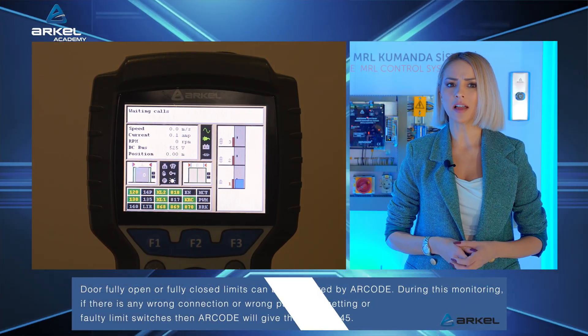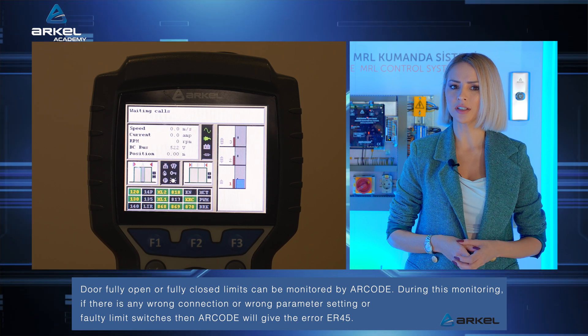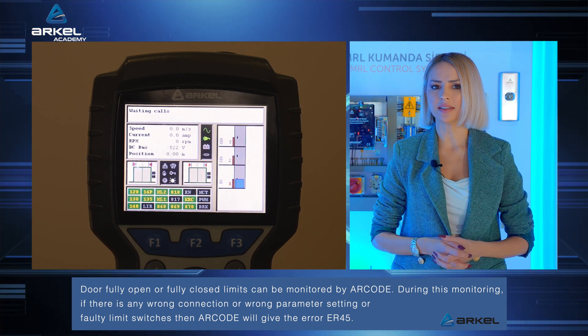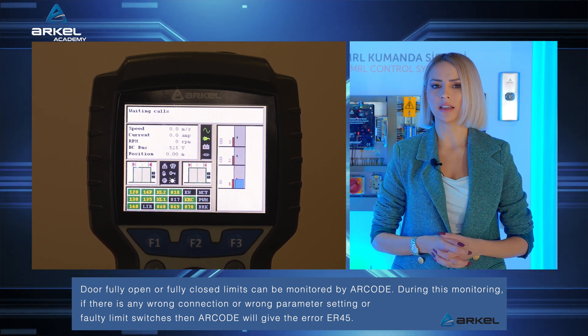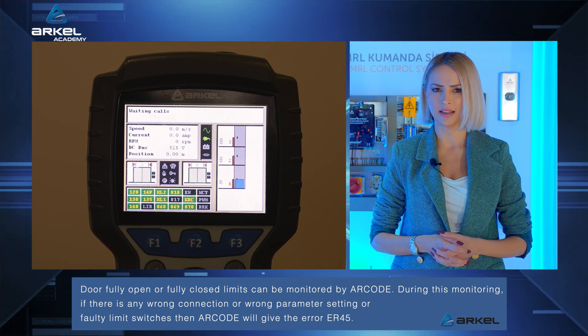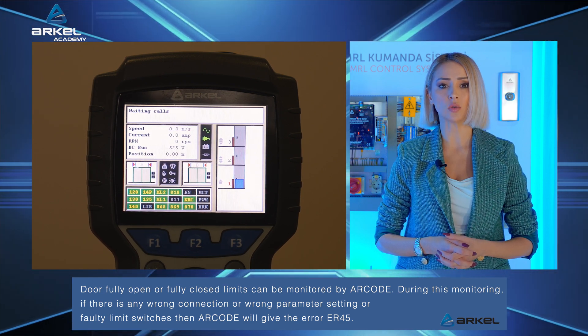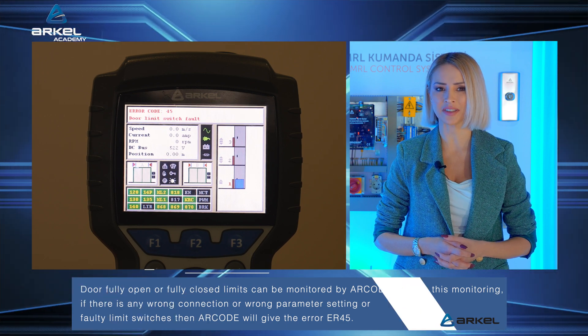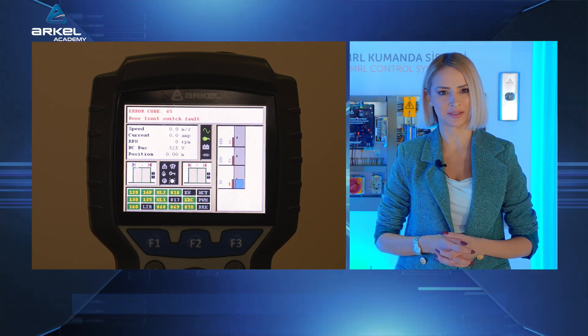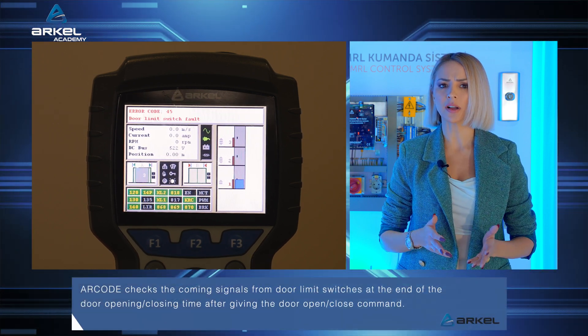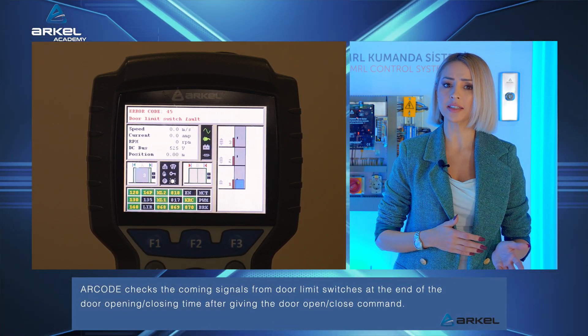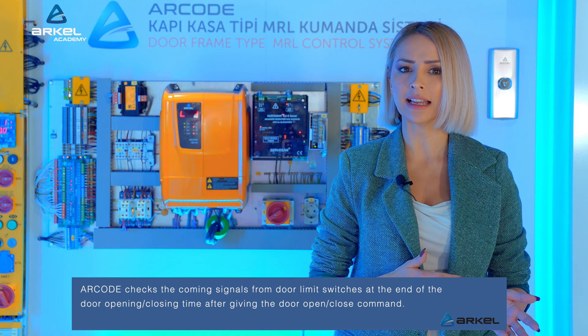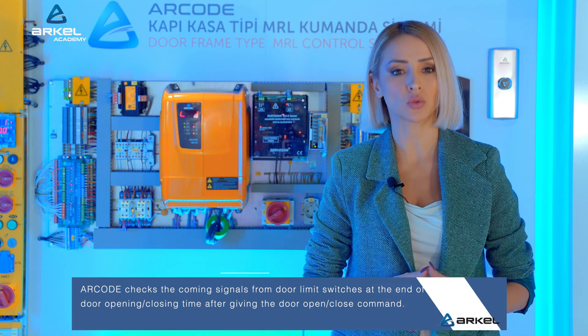Door fully open or fully closed limits can be monitored by ARCODE. During this monitoring, if there is any wrong connection, wrong parameter setting, or faulty limit switches, then ARCODE will give the error ER45. ARCODE checks the signals coming from door limit switches at the end of the door opening and closing time after giving the door open or close command.